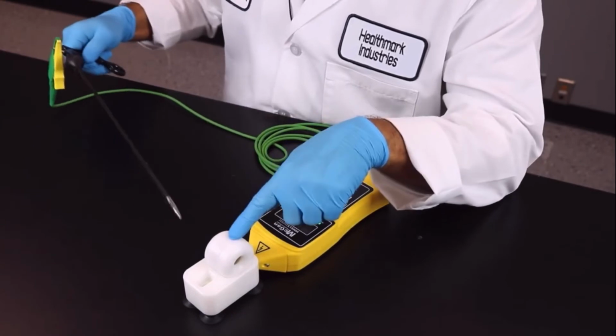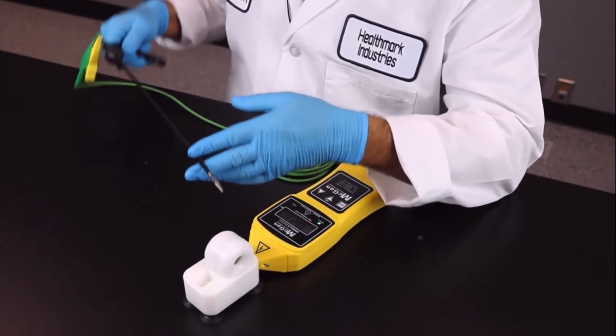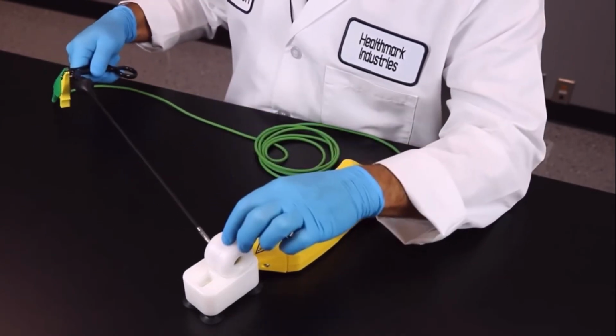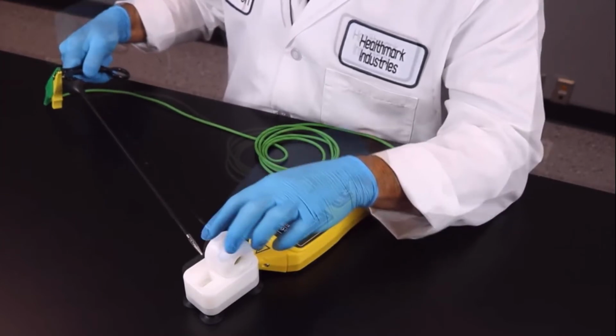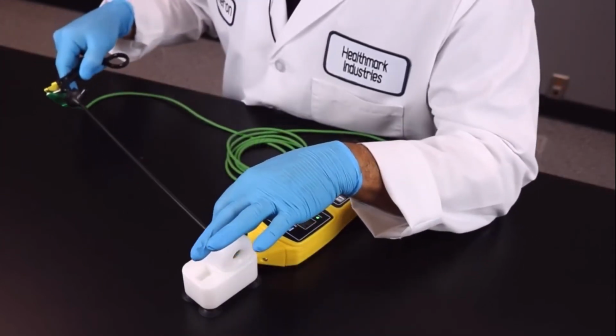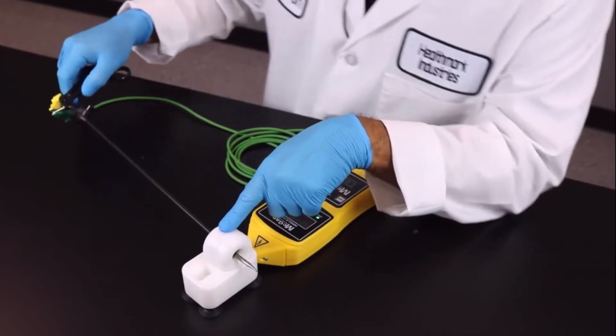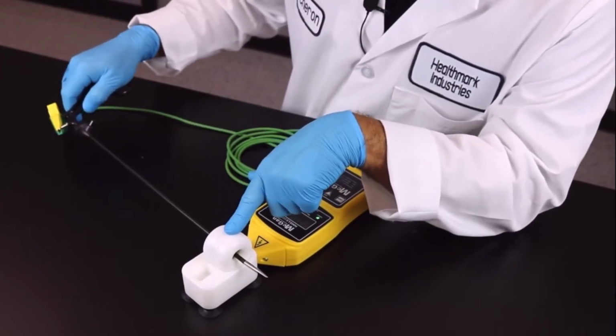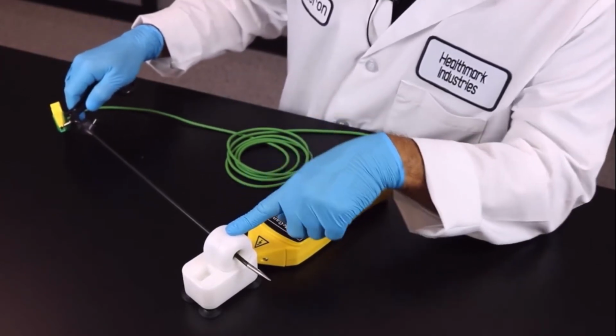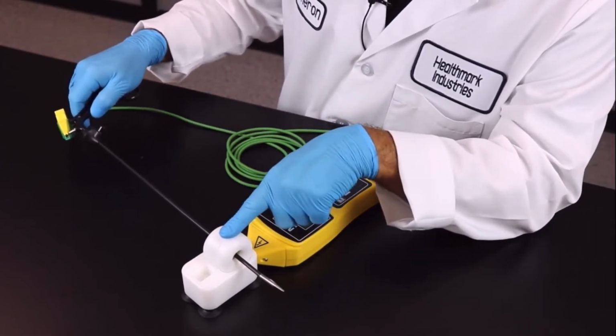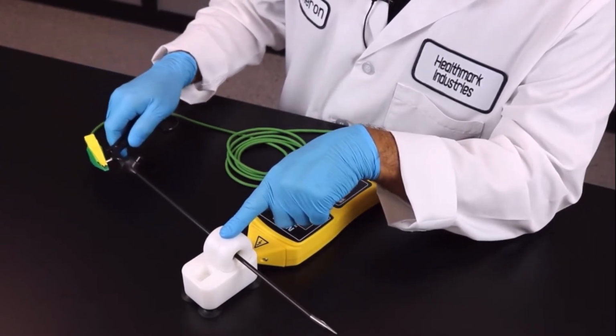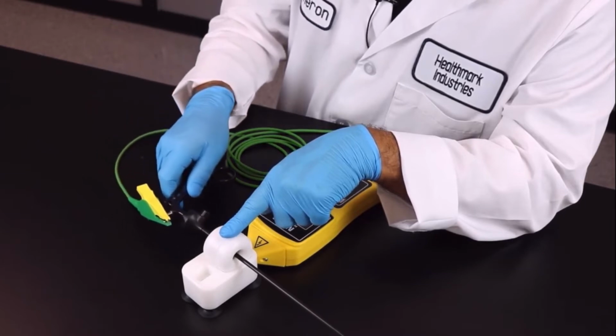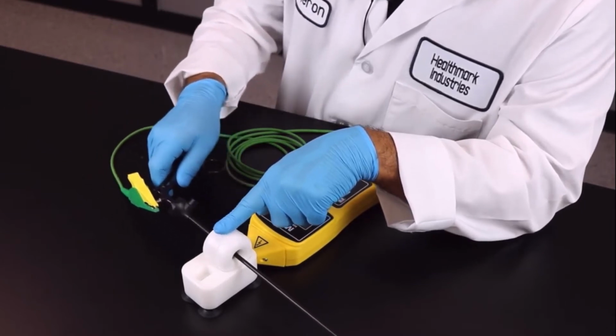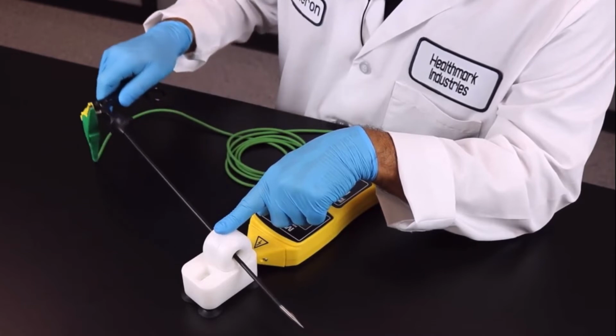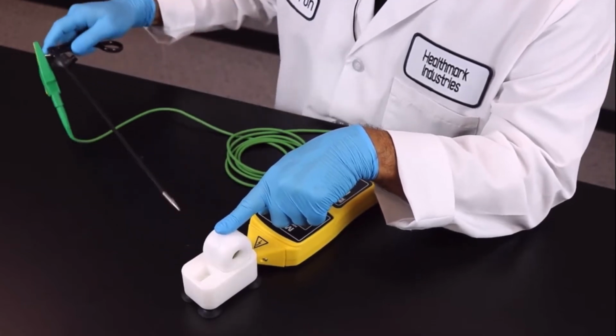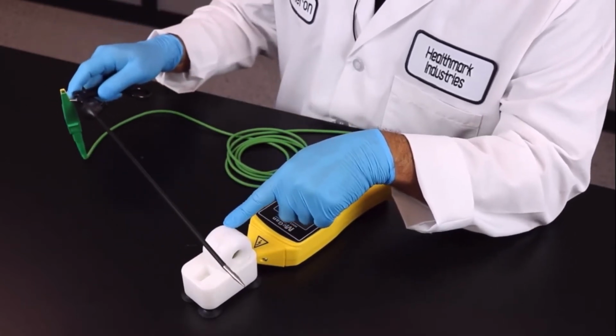Now, to begin, we want to make sure that the laparoscopic instrument is grounded. So in the non-insulated part, it should go off. Once it's grounded, you're going to go in slowly, especially at this distal end here, because as you can hear and you can see by the alarm, it's going off. You want to go slow all the way down the shaft to the proximal end. Then you're going to go all the way slow back to the distal end. And that's how you test a laparoscopic instrument.